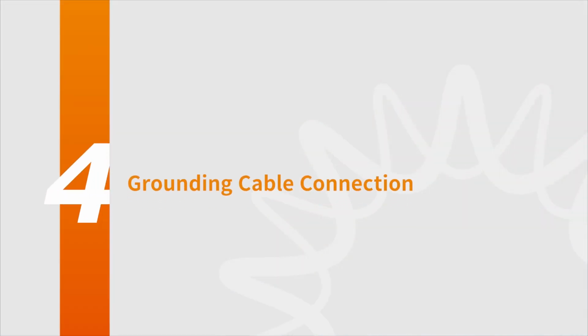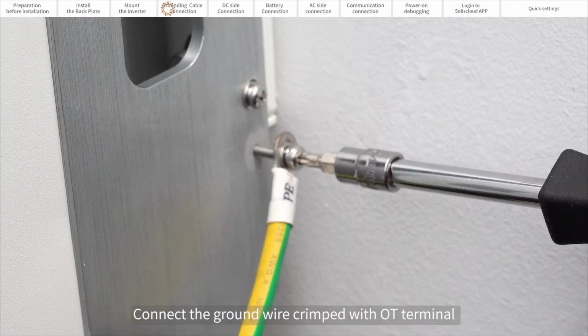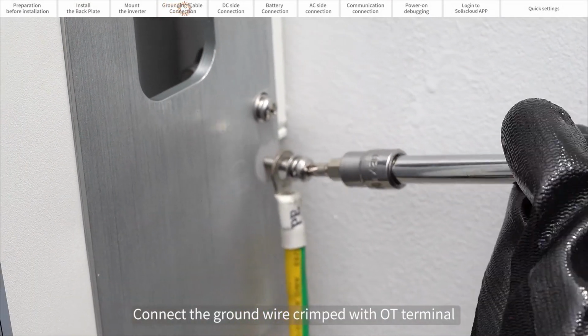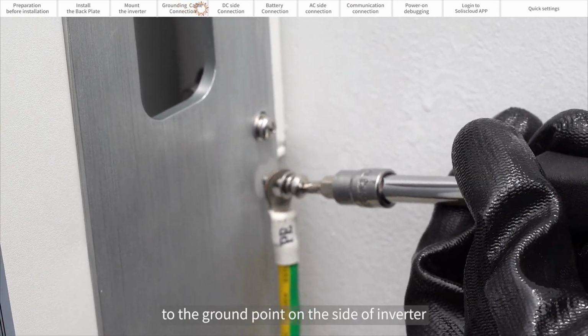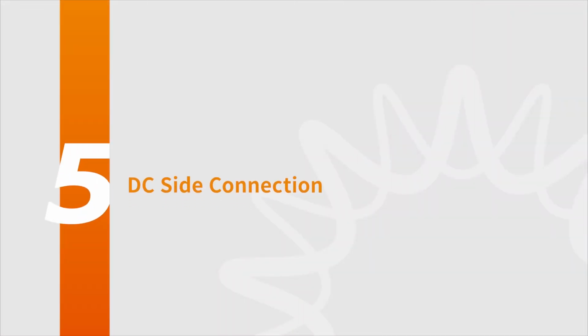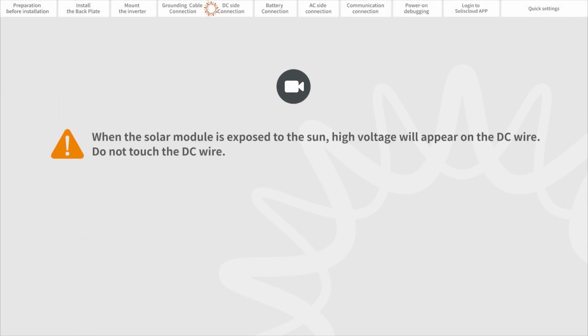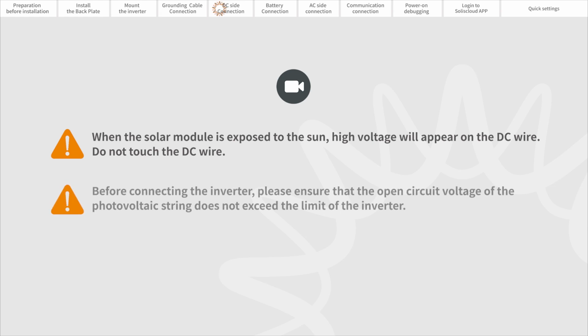Part 4. Grounding cable connection. Connect the grounding wire crimped with the OT terminal to the ground point on the side of the inverter. Part 5. DC side connection. When the solar module is exposed to the sun, high voltage will appear on the DC wire. Do not touch the DC wire. Before connecting the inverter, please ensure that the open circuit voltage of the photovoltaic string does not exceed the limit of the inverter.